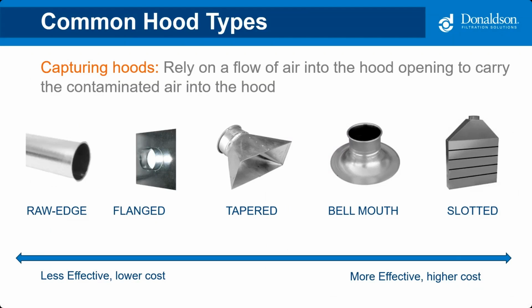The most common hood style is a closed capture hood, which relies on establishing a general flow pattern into the hood opening to produce a capture velocity at a specified distance from the hood. Here you see the 5 most common types of capturing hoods. The most common that we see are the slotted hood and the tapered hood in the field.